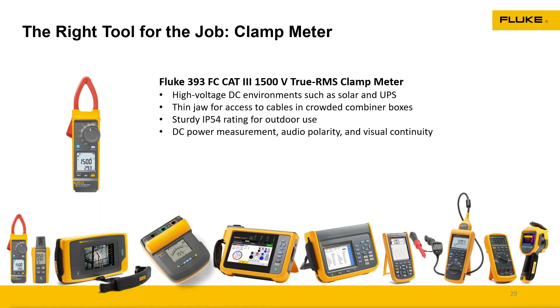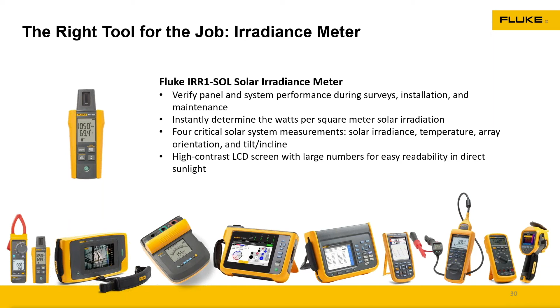It's your watts per meter squared going into the solar panel. From that, you're going to get a curve analysis and be able to determine, based on that irradiance, how much voltage and current should be coming out of the panel. This is huge because if you've got panel failure, maybe a degradation of the panel, this one tool alone would allow you to determine that, obviously with your clamp meter and your DMM.